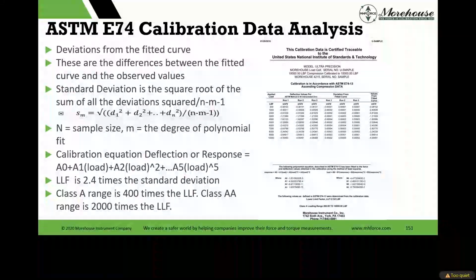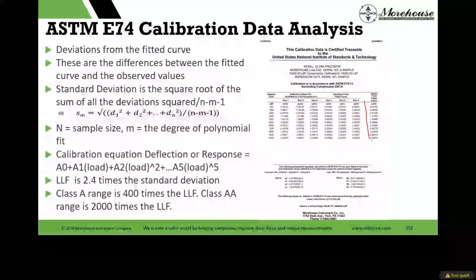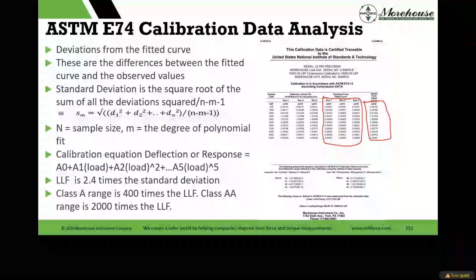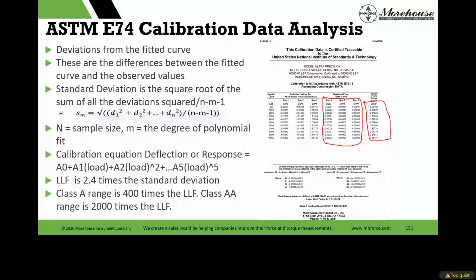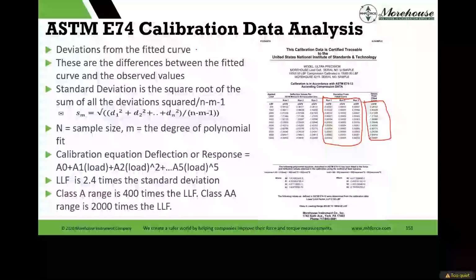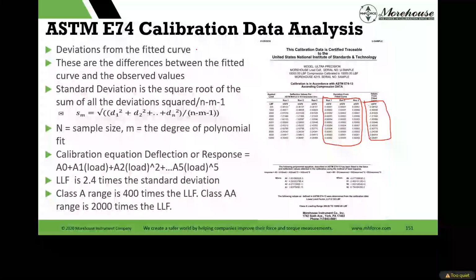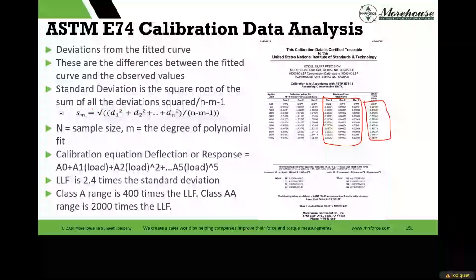And then, so after we've plotted this curve and we've done it correctly, plotting them against each other, we figured out the degree fit, used the annex to select everything. Basically what E74 does is then it says, okay, I'm going to take the deviations from this curve. I'm going to take these values minus the observed values over here, and I'm going to plot the deviation. So that's this piece. And then they root sum square these in this equation.